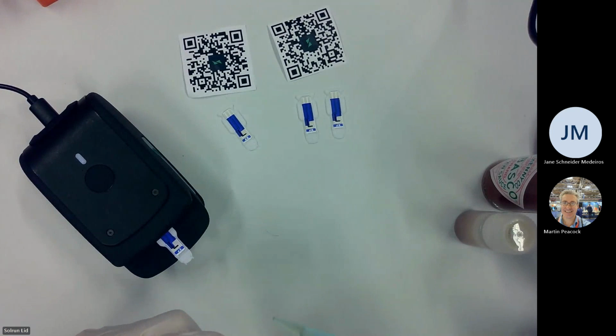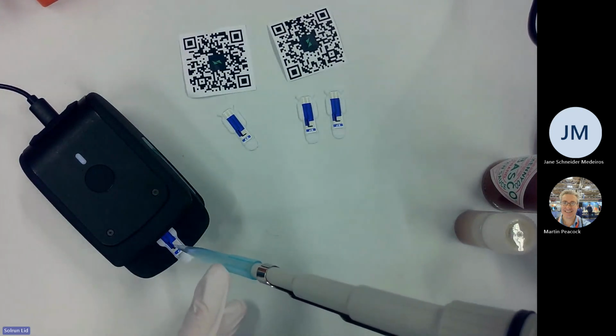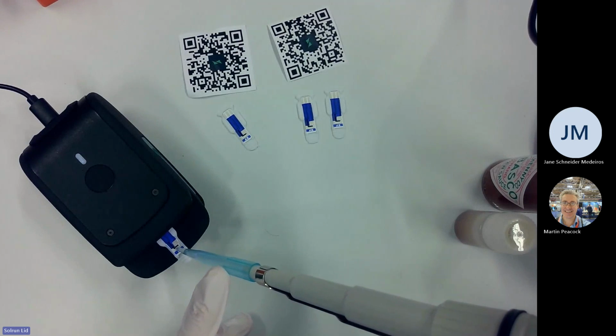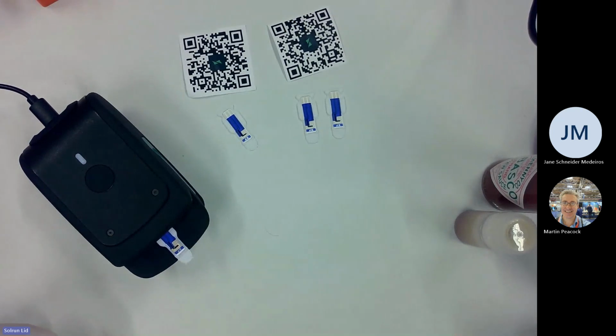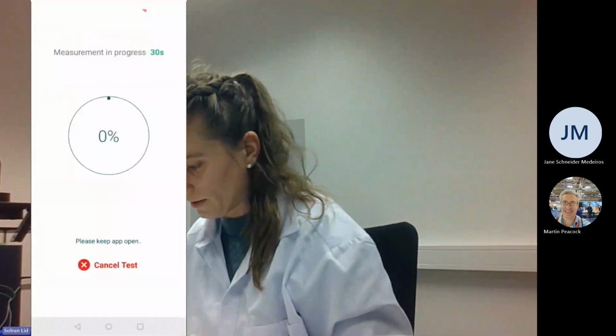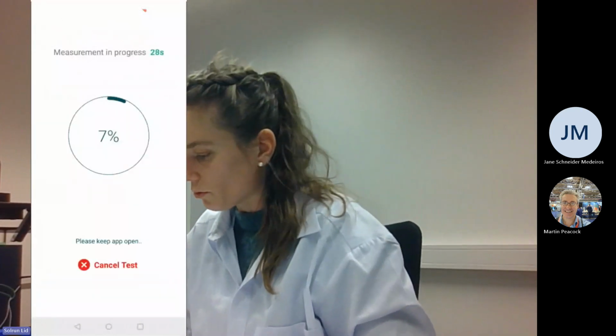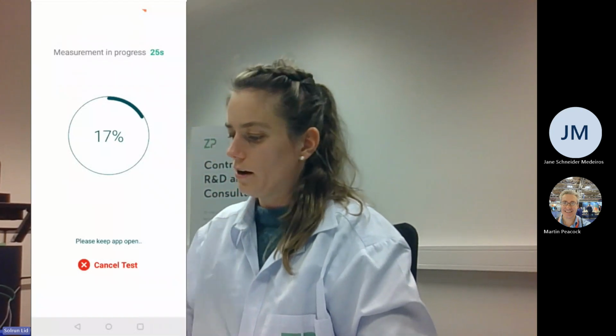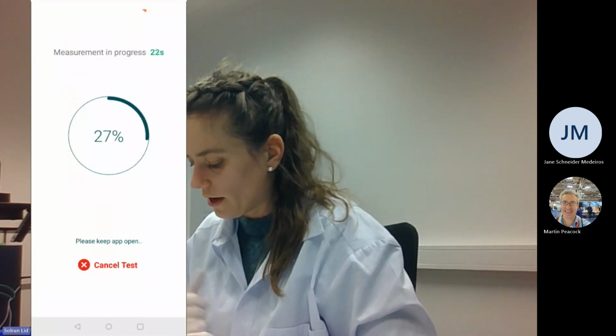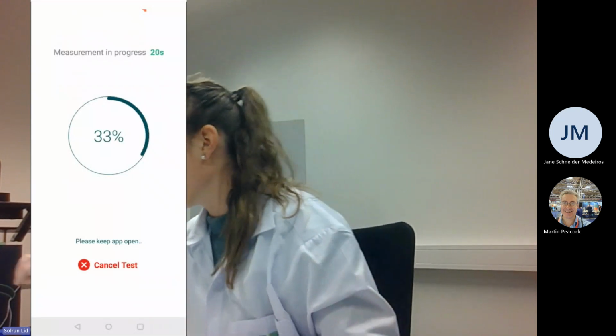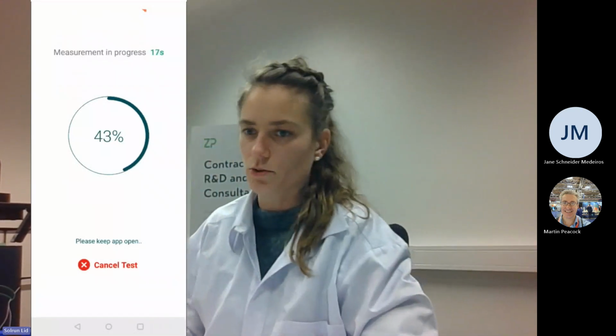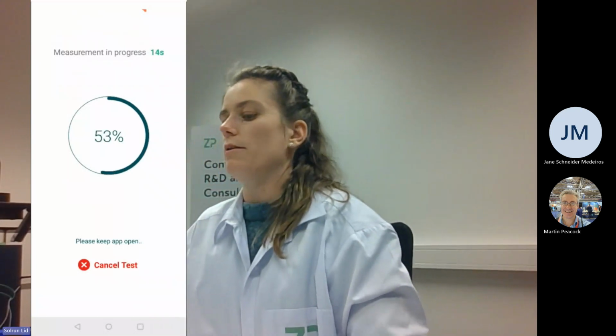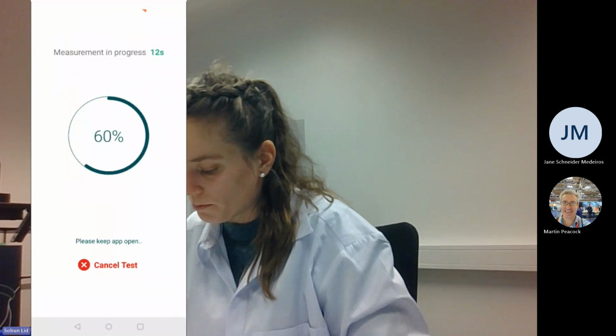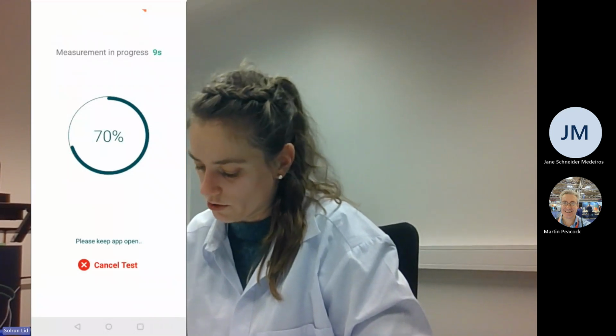And then when I've added the sample into the pipette tip, I will dispose of it on the electrodes of the sensor. So be careful not to scratch the surface of the electrodes. Then I will go to the app and I will click start measurements. So it's important that you don't wait too long between pipetting the sample onto the sensor and starting the measurement, because capsaicin is very fond of the surface of the electrodes. So if so, your results will appear to be spicier than it is, or higher concentrated.